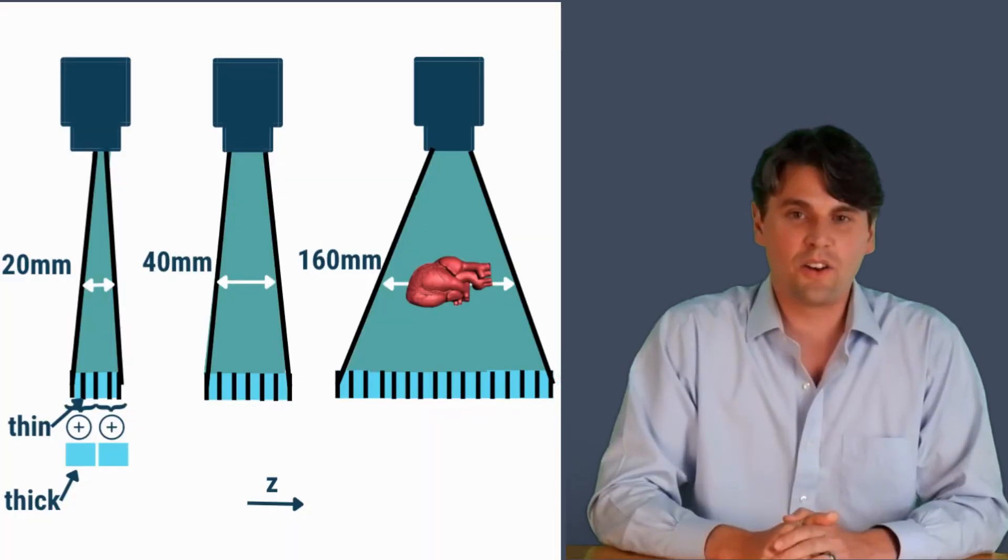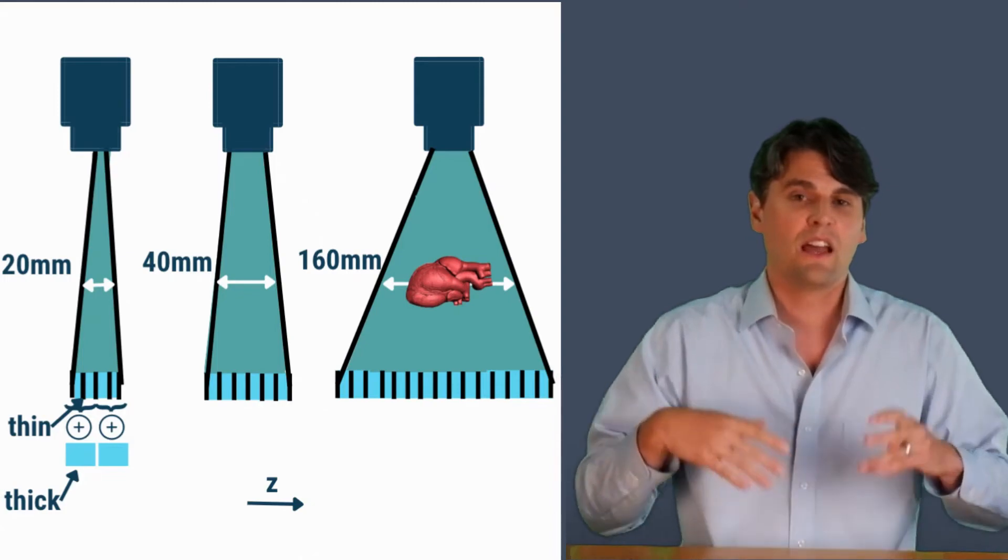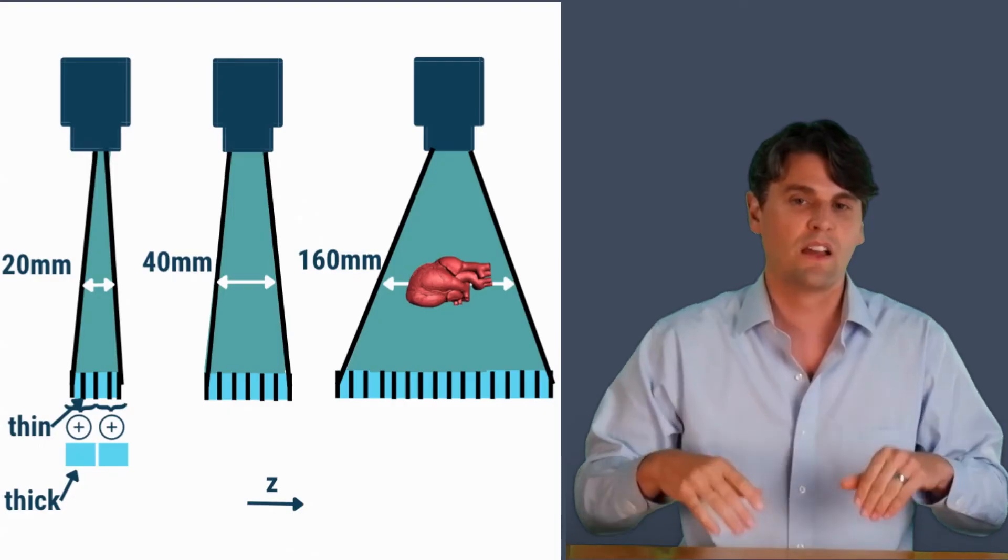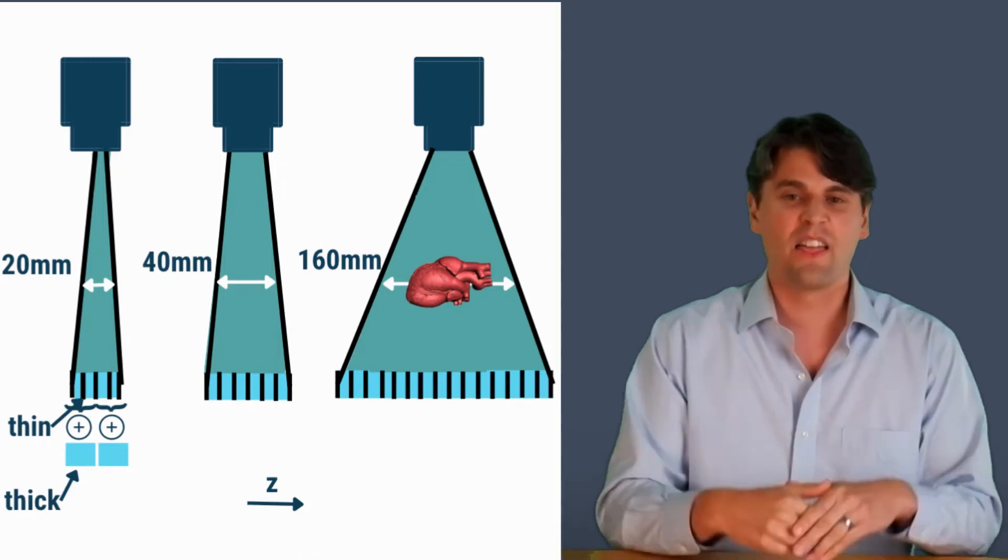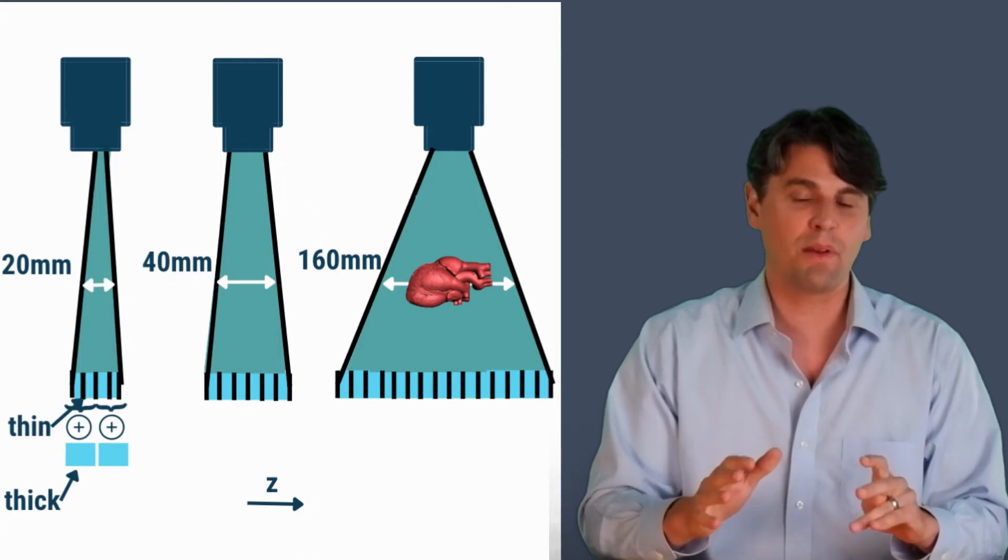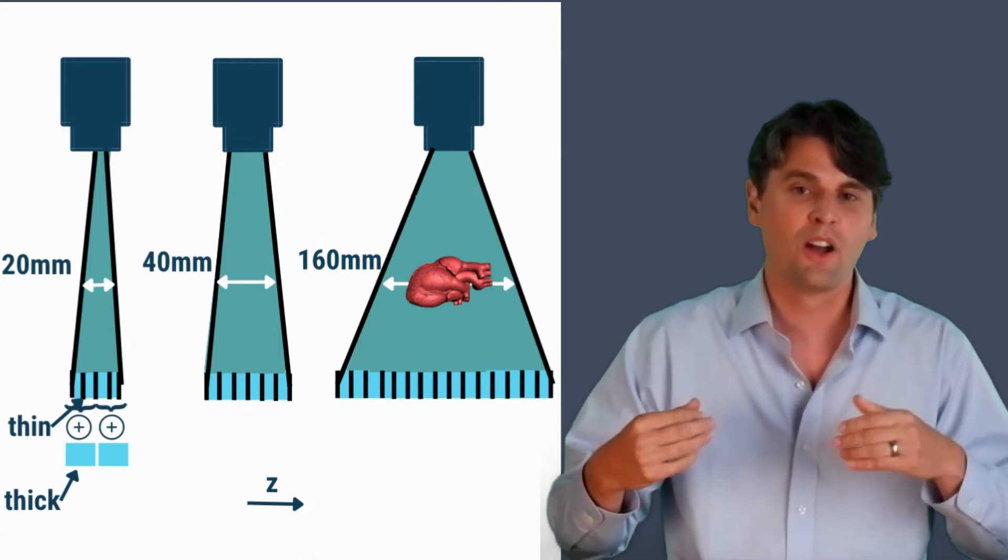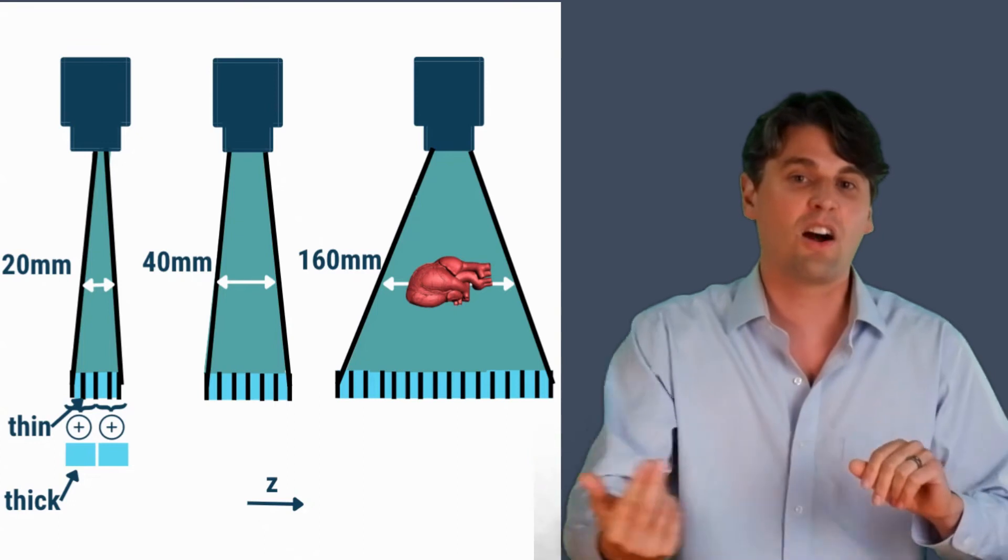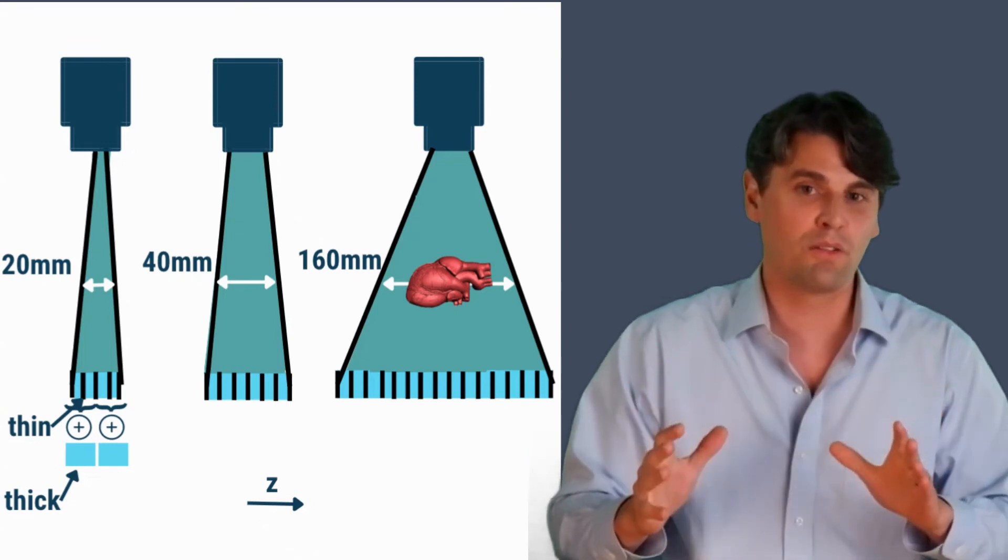It's about the 160 millimeter collimation is that most hearts are about 140 millimeters or less. You can really well cover the vast majority of human hearts with this type of a system, and you can get an image of the human heart which is very consistent and comes from just one rotation or actually a fraction of one rotation.